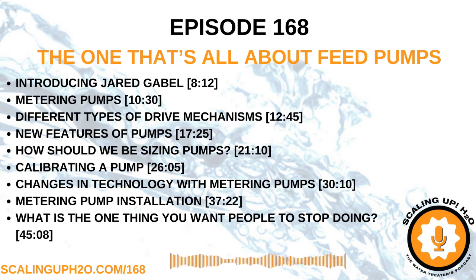So I can either control the frequency of those pulses, or in the conventional dosing world, you can set the stroke length. That really takes it from a full sweepable volume of that diaphragm through the dosing head and cuts it down by a percentage. Usually you can set it to like 50 or 20% suction stroke, or like a 50 or 20% frequency. Then you multiply those two percentages together, and that's your feed rate of the maximum capacity of that pump.